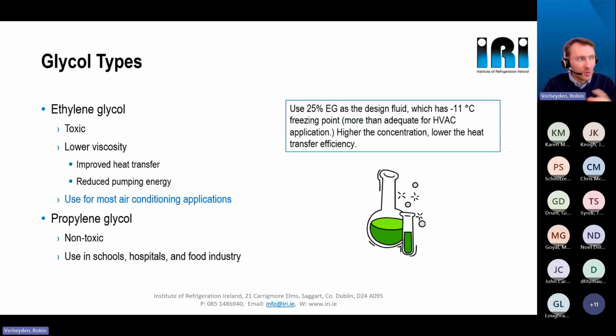Now, to give you some more insight about internal melt, the typical fluids used are ethylene and propylene glycol. So when would you use ethylene glycol? Ethylene glycol has a lower viscosity and is in general more efficient to use for ice thermal storage. But it is toxic. Therefore, in a lot of food applications, you will see the less efficient propylene glycol, because it's non-toxic. So the typical food industry, hospitals and schools use propylene glycol. All the rest we mostly see with ethylene glycol today.